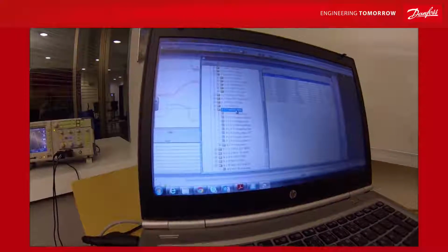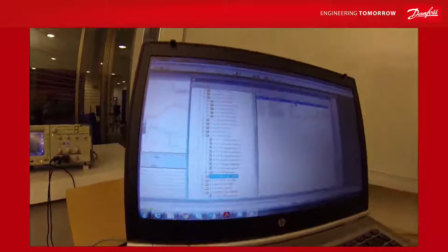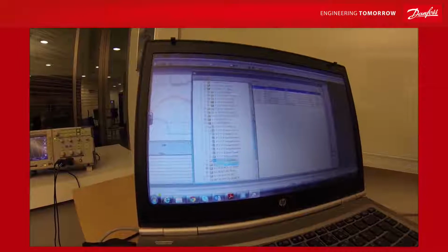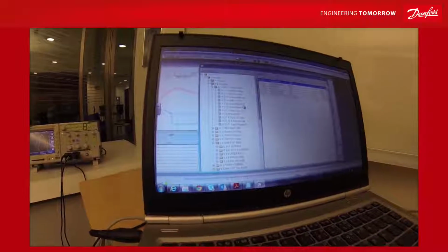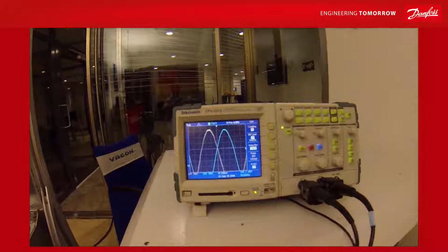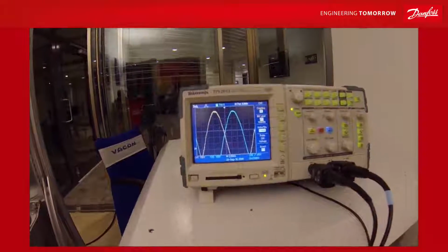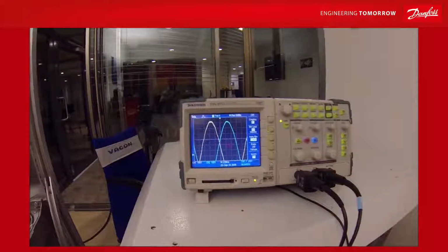Okay. We have the microgrid sync to external grid. Here we have an offset now of 1500. Is that okay? I'm not sure. Let's activate the command for sync. Input signals, net synchronization, go to the RAM, and whew! It did something, but it missed the grid. Well, 1500 was sure not okay, and the sync error is a lot off. So let's adjust this.